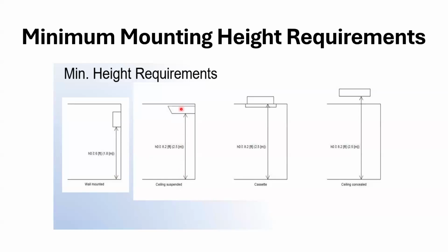Ceiling suspended type unit, that would be like the PCA type unit, which is not a real common unit, but if you're using that particular unit, then that's what they're showing right here: greater than 8.2. Same thing on your cassettes. That could be a 4-way cassette, or the MLZ 1-way cassette. So again, 8.2 feet from the floor to ceiling. And then here are your concealed ducted units, like your PEAD. Those are the height requirements they're requiring now, to prevent the refrigerant settling at those low levels.